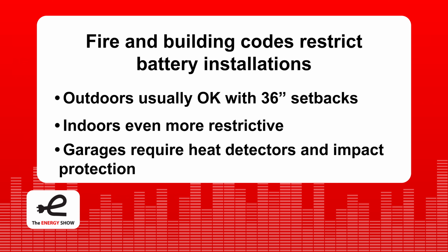So in general, outdoors is okay. Pretty much everybody allows you to put battery systems outside, with a couple of constraints we see in California and some other states. Current codes enforced in most of California say batteries can only be installed in garages and basements if you have an automatic heat detection system or automatic sprinklers, and if you put in bollards or curbing to prevent your car from knocking over the battery. Sounds kind of crazy, but these are the rules.